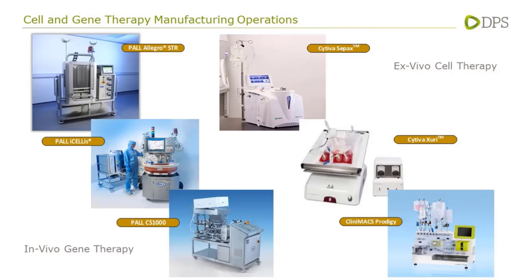Looking at ex vivo cell therapy using CAR-T as an example: CAR-T being a personalized medicine approach, the batch size always relates to one patient. Small scale benchtop equipment — such as a separation system and cell expansion system — would be used in the manufacture of these processes. The CliniMACS Prodigy provides an example of a fully integrated production line for a cell therapy process, whereas other equipment separates the unit operations into individual pieces of equipment.